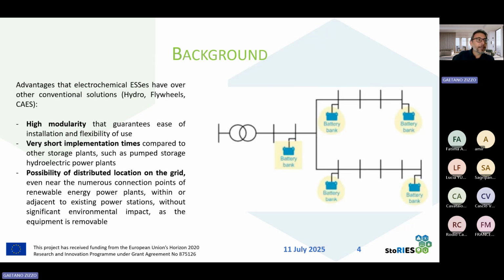So we can install a given unit of storage in a node of the grid, and then if we want to increase the amount of storage in that node, we have only to buy another unit compatible with the first one that can be managed by the same battery management system at that node. And this is a great simplification for installing a regulation device. The second advantage is the very short implementation time. This is a fundamental characteristic, in particular, if we compare the electrochemical storage with other storage solutions, for example, with the hydro pump storage.